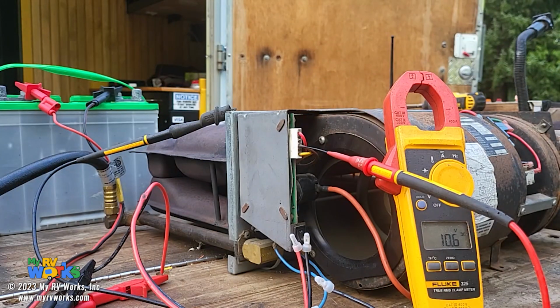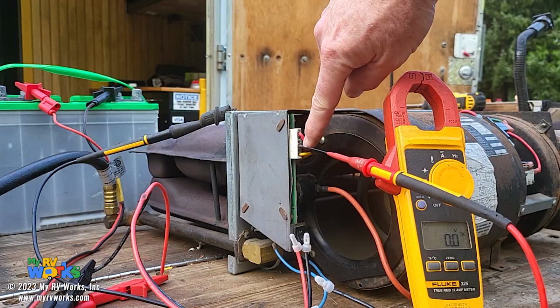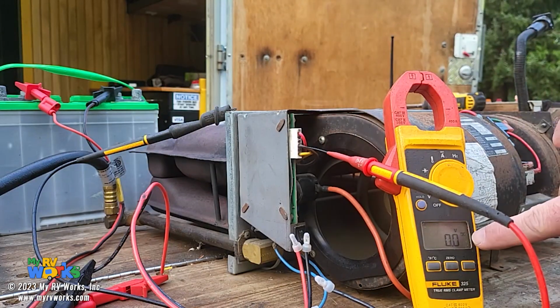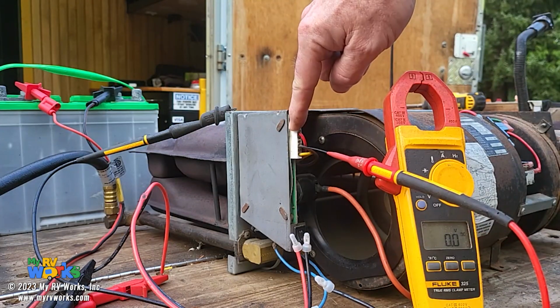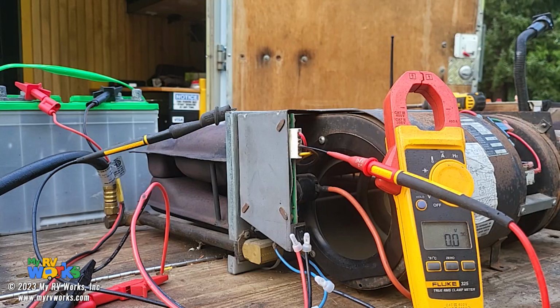Some of your furnaces will have what's called a soft lockout. Soft lockout is when I try 3 times and cannot get it to ignite. At that point, I will basically start a timer for 1 hour, and after 1 hour, I will try 3 more times. After that 3rd time, if I still cannot ignite, I will go into what's called hard lockout, meaning I will never, ever try to start again.